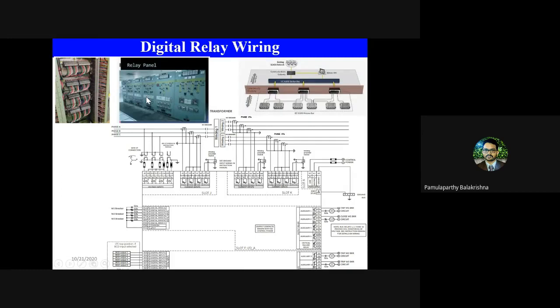But in the context of the digital substation, or the advanced digital substation concept, we are avoiding all this wiring. All that is required for a relay is just a fiber optic communication cable. All the signals present in the field are digitized in the field itself by what you may or may not have heard of as merging units. The job of the merging units is to digitize the entire data in the field, near the transformer where it is installed, and all the digitized data is communicated on a dual fiber optic cable, and the entire data comes to the relay by a single fiber optic cable connected on the backside.